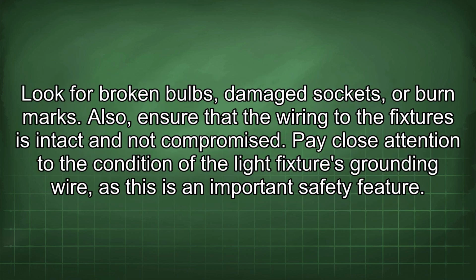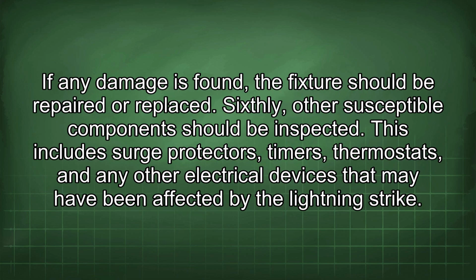Fifthly, lighting fixtures should be checked. Look for broken bulbs, damaged sockets, or burn marks. Also, ensure that the wiring to the fixtures is intact and not compromised. Pay close attention to the condition of the light fixture's grounding wire, as this is an important safety feature. If any damage is found, the fixture should be repaired or replaced.